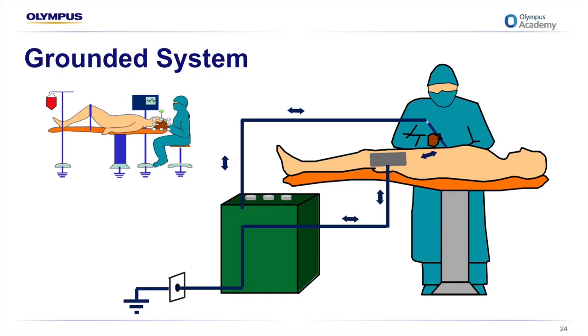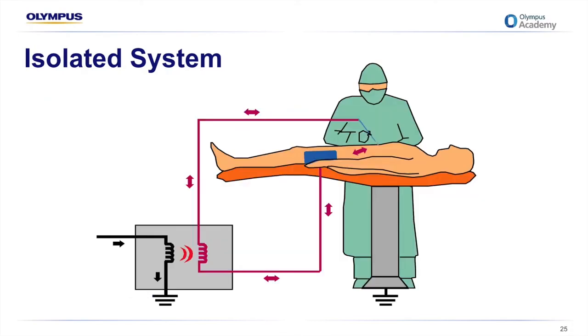Grounded generators use return electrodes that may consist of one of the following: a metal plate that is coated with conductive gel, a return electrode with a dry conductive adhesive surface, a return electrode coated with a water-based gel, or a return electrode coated with the preferred hydrogel adhesive that is high in moisture content. All of these return electrodes have a single plate configuration. This next slide depicts an isolated generator. Note how the current from the wall outlet enters the generator and then returns to the ground. As it passes through the generator, an isolated current is generated.